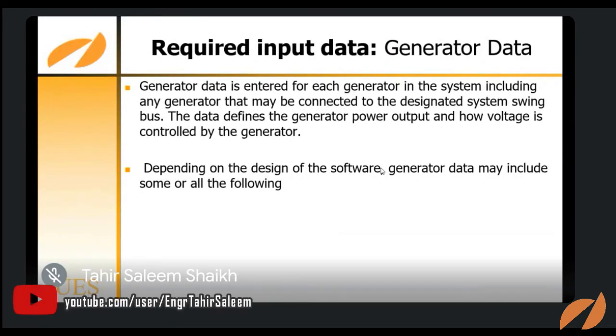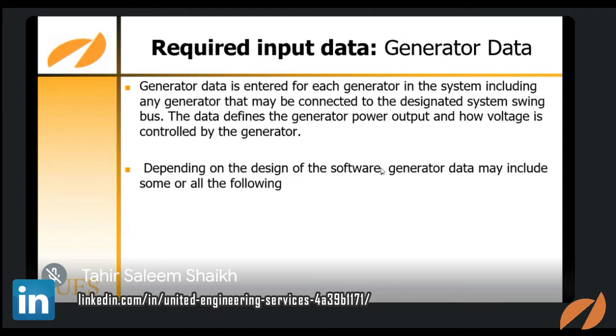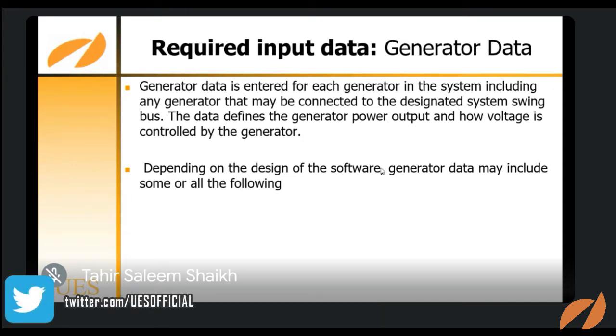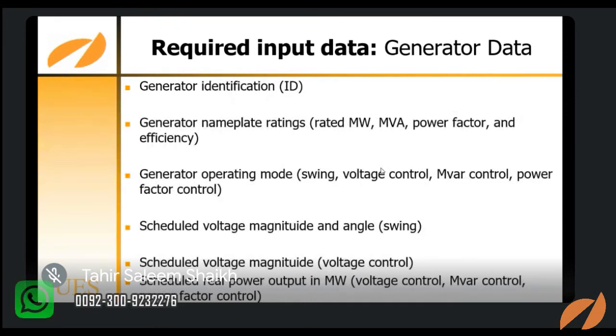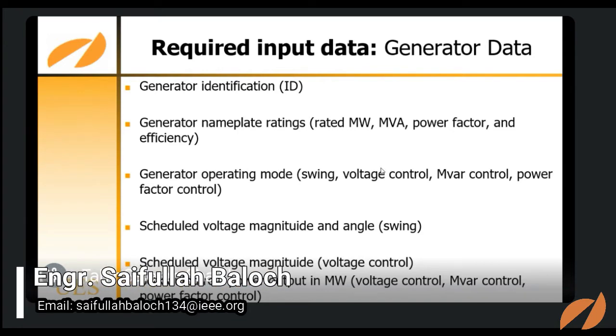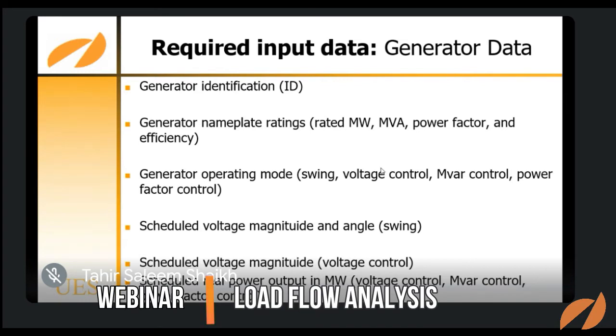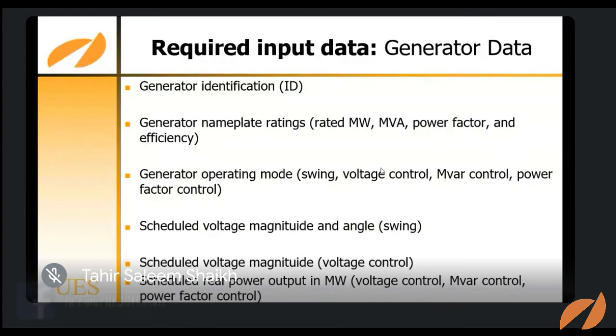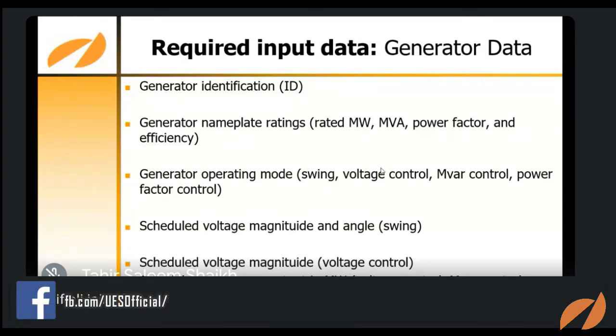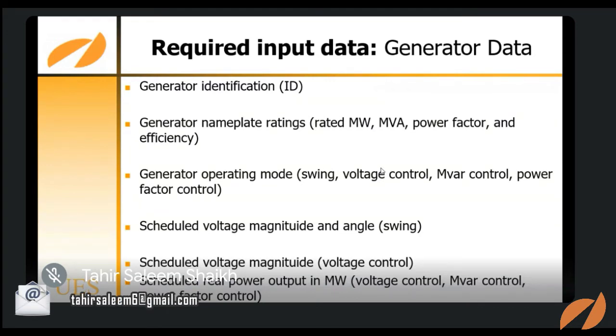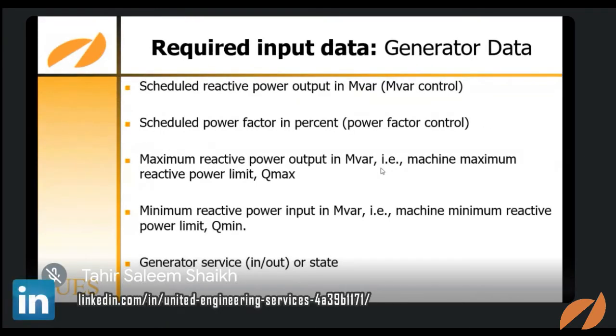Generator data is also defined on the nameplate, or if you are assuming any data, you need to have voltage, current, and rated power. These depend upon generator identification, generator nameplate ratings, and generator operating mode: swing, voltage control, MVAR control, power factor control. These are the different operating modes. In the next two or three slides, we are going to explain such types, and this will also refer to the generator operating mode. Scheduled voltage magnitude, that is voltage control, and scheduled real power output in megawatt. So these are the different data which you need to put in the software.